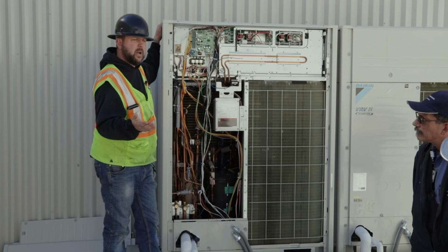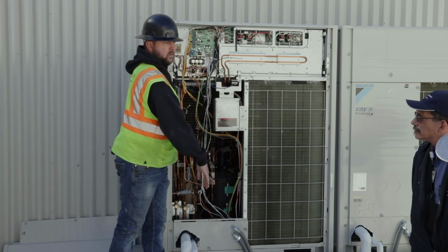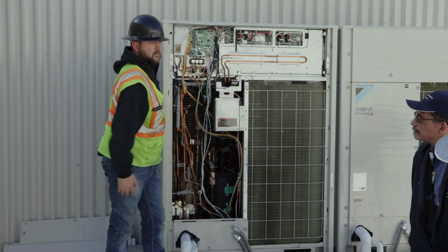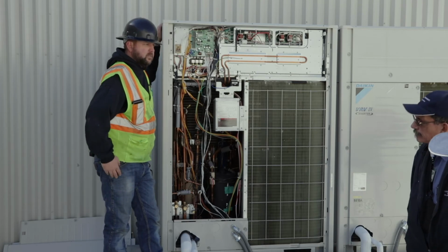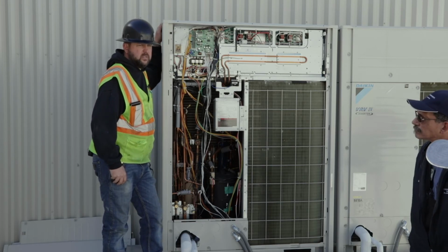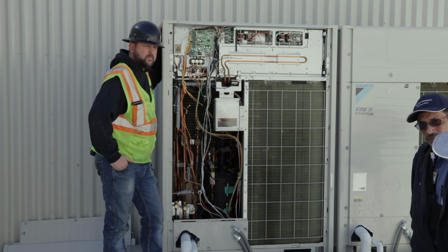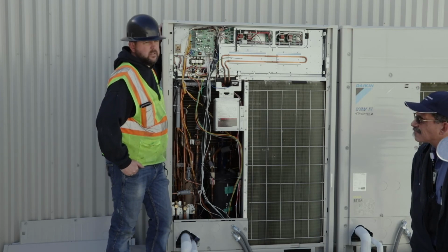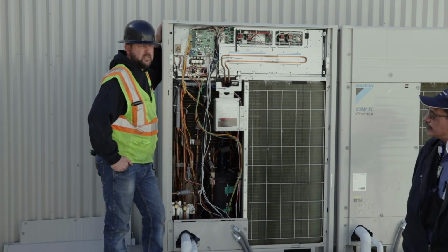But if you do have to kill power, say a fan motor went out on it or whatnot, come up here, turn the power off to both of these, run down there, turn the power off to that fan coil, come back up here, flip the disconnects back on, it'll reinitialize, and it just won't see that fan coil no more. So that's the easiest way to do it. That iTouch manager, that saves all the information that you put into it already? Yeah. When it reinitializes, it won't cause any problems with that? No. So, yeah, that's how I always do it. Seems to be the easiest.